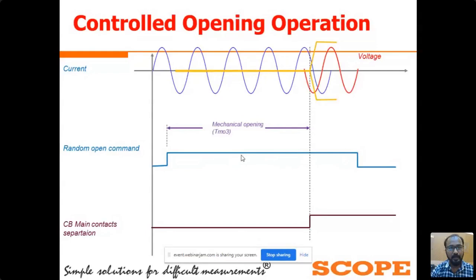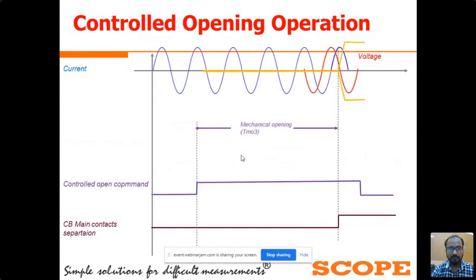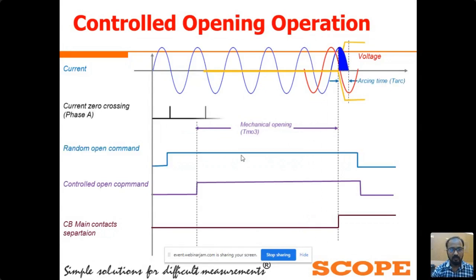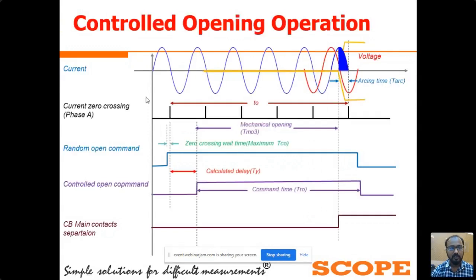Now we will see the controlled opening operation of the circuit breaker. In this slide, we can see this is the system current waveform. This continuous waveform is the system current waveform. The waveform in red is the system voltage waveform, and this dark line in orange is the dielectric strength between the CB contacts.